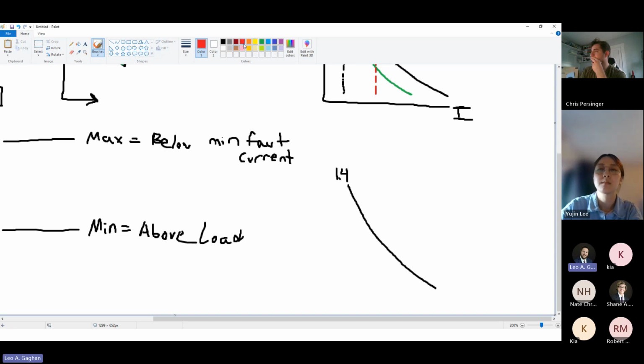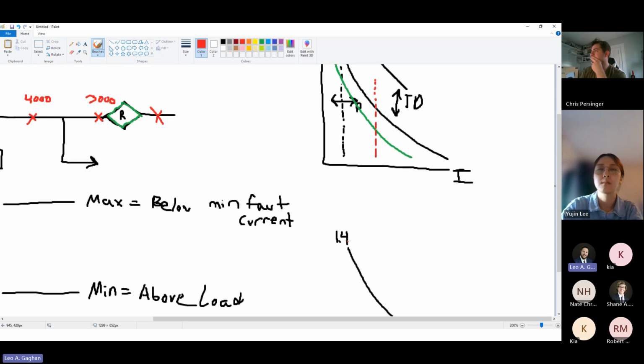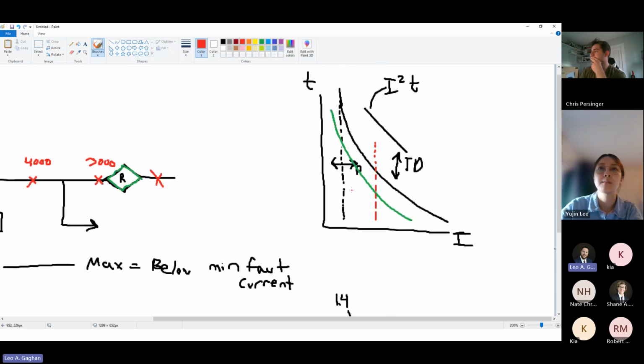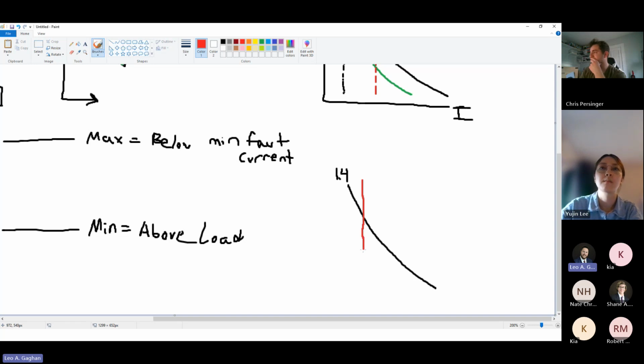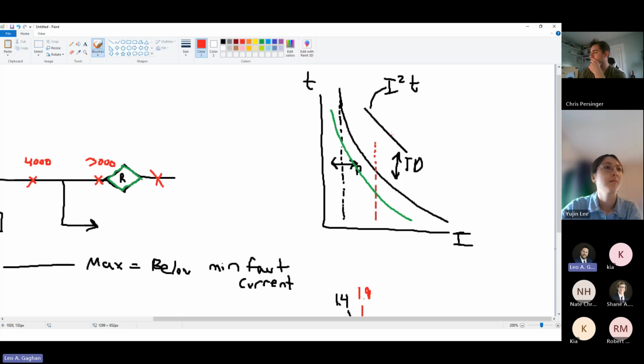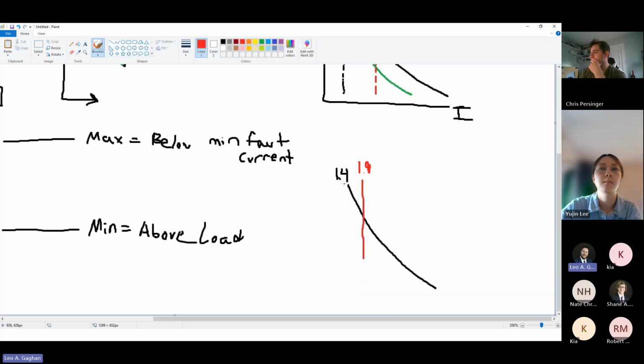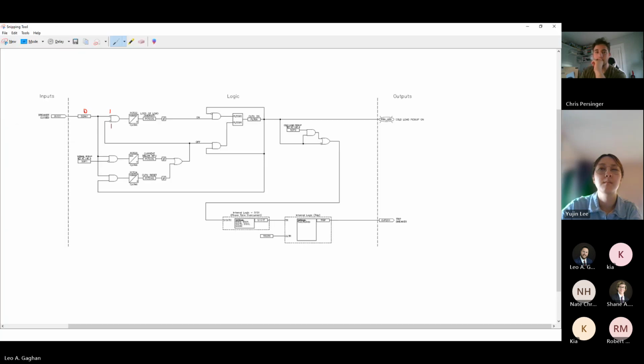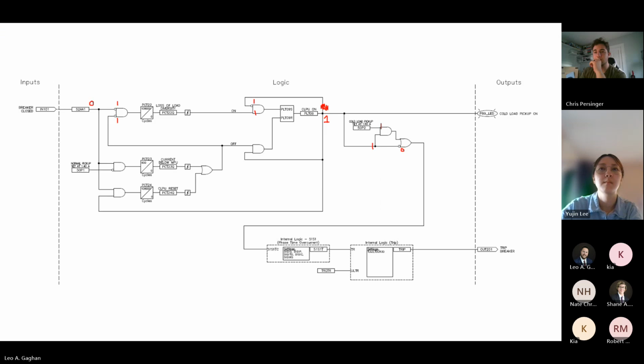And basically what we did, I like to use the word snipped. We snipped off the back end of this curve. The curve didn't move, right? If we would have changed that pickup, we would have gone left, right. But we didn't do that. We had a separate element torque control it, and we effectively snipped it at 1.9. So now everything here is going to look the same. It's going to coordinate with that damage curve the same. It's going to coordinate with that recloser the same. We just snipped off that part of the curve and effectively made the pickup 1.9.